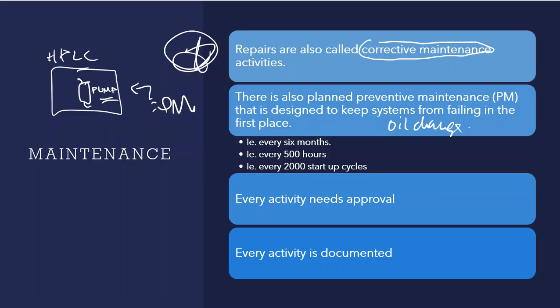So, for instance, preventive maintenance, again, can happen every 6 months. Time frame wise, maybe every 500 hours that the instrument is on. Maybe every time you start the machine up. So every 2,000 times that the startup process begins, you're going in and doing something, preventive maintenance or PMing that instrument in some form or fashion.